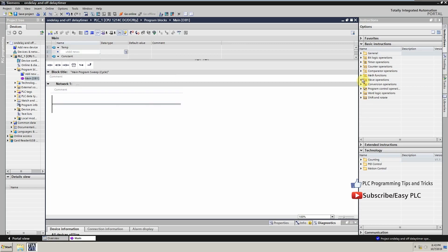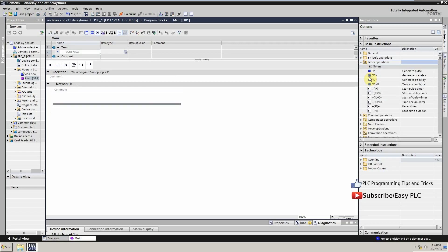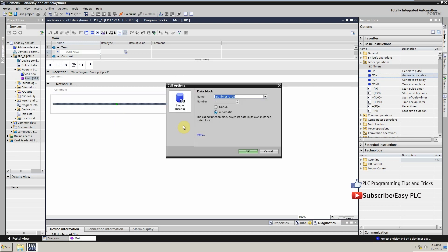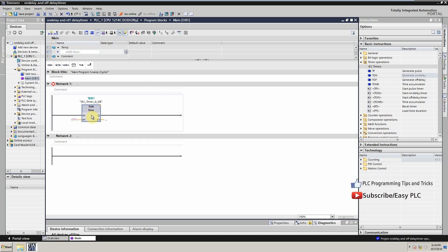First we will start with the ON delay timer. Just drag and drop the timer command on the ladder and it will create a data block for this timer. As you can see, this timer has IN and PT inputs. IN is the input to start the timer, PT is the preset time, and Q is the output which will be turned on with this timer.